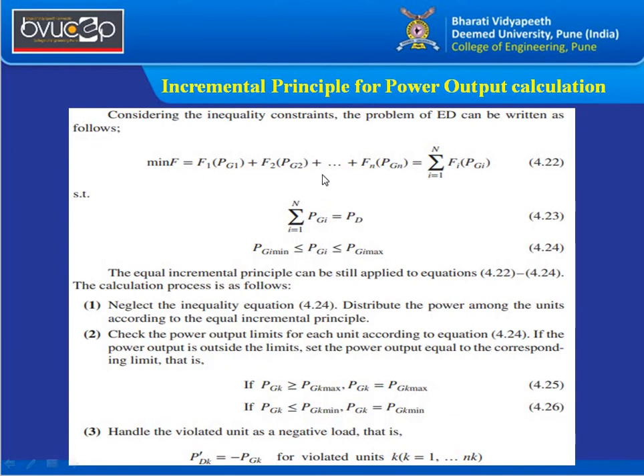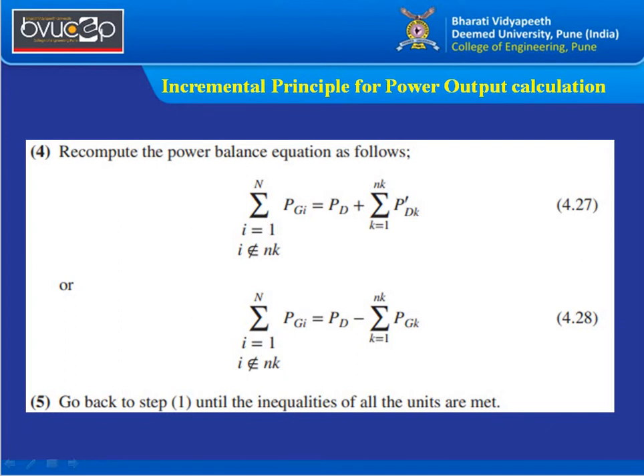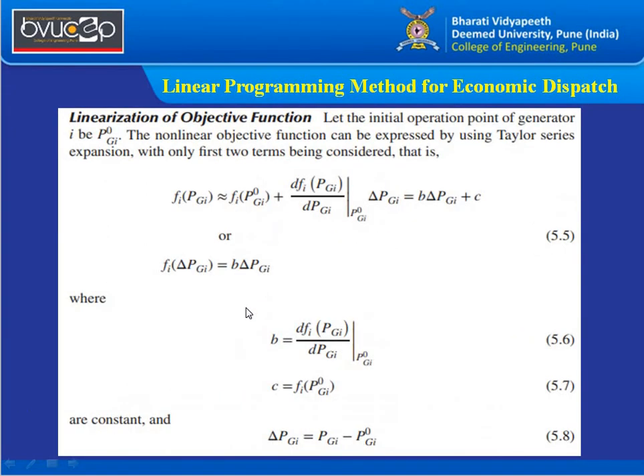For the incremental principle with power output constraints (equations 4.22 and 4.24), the procedure is: Step 1 — neglect constraints and distribute power among units by the equal incremental principle; Step 2 — check limits: if Pgk > Pgk_max, set it to maximum; if Pgk < Pgk_min, set it to minimum; Step 3 — avoid negative load violations using the Pdk term for k = 1 to Nk; Step 4 — check the power balance equation. If inequality constraints are satisfied, accept the solution; otherwise return to Step 1.